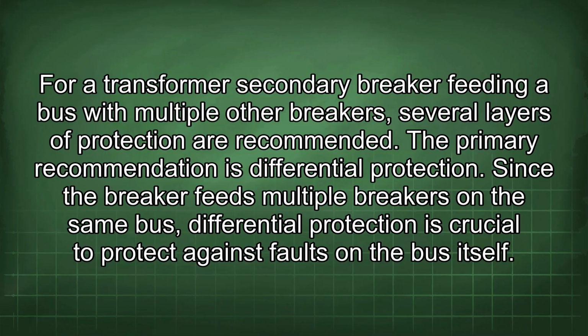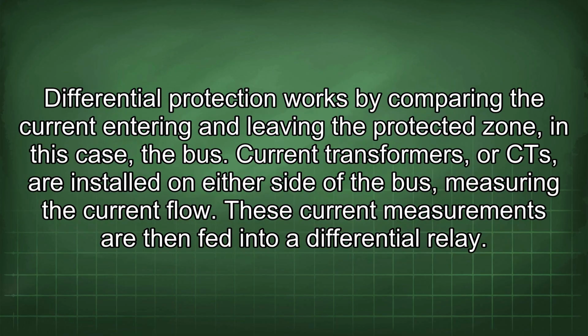For a transformer secondary breaker feeding a bus with multiple other breakers, several layers of protection are recommended. The primary recommendation is differential protection. Since the breaker feeds multiple breakers on the same bus, differential protection is crucial to protect against faults on the bus itself. Differential protection works by comparing the current entering and leaving the protected zone, in this case, the bus.